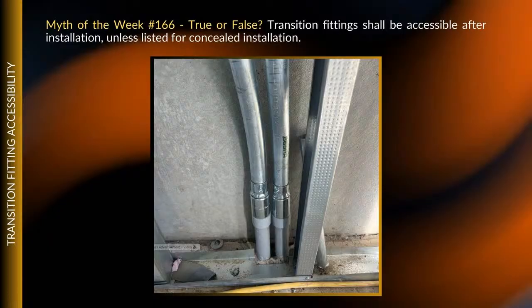There may be listed transition fittings that go from PVC to EMT, but I don't know, there are a lot of different transition fittings I don't think they make. But to me, I think the only way you could really do this legally is to have a PVC male adapter that threads on with a listed EMT to rigid transition fitting, and then that would be listed for concealment. You can obviously see this is going to be buried behind drywall.